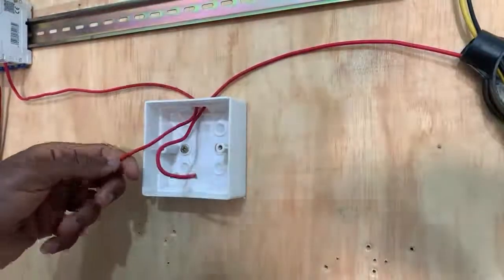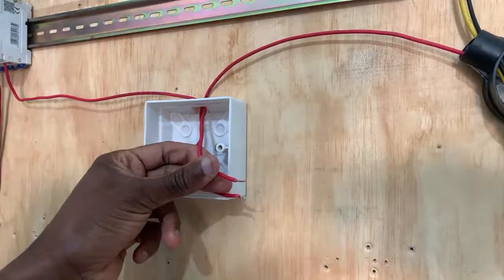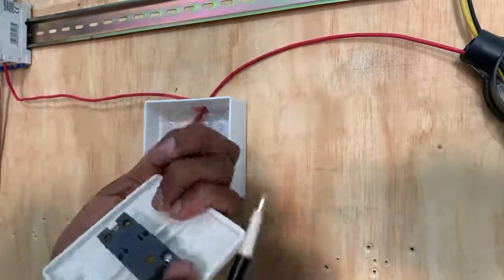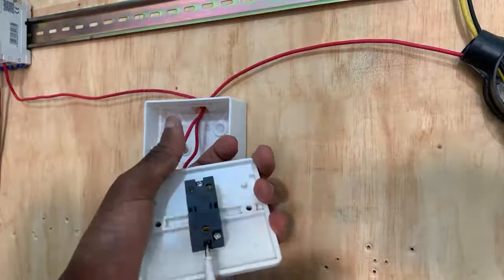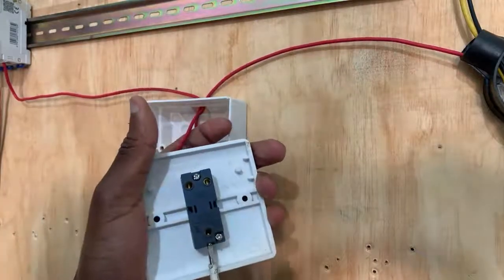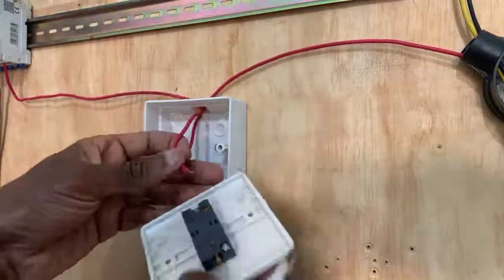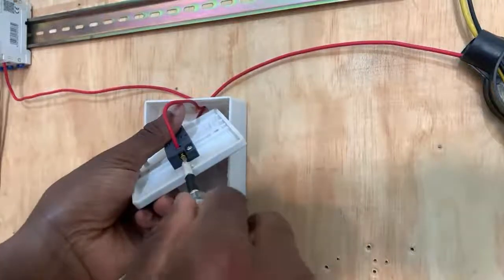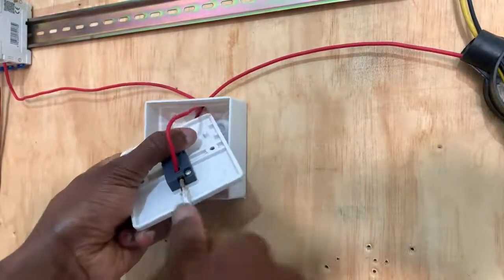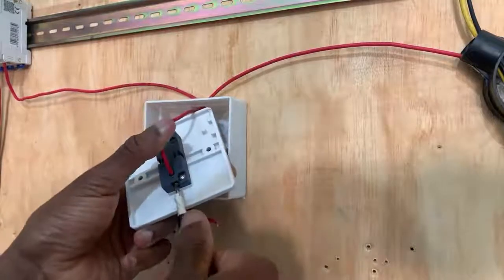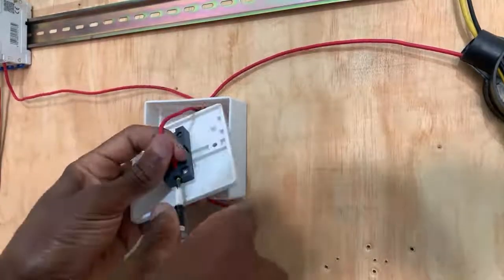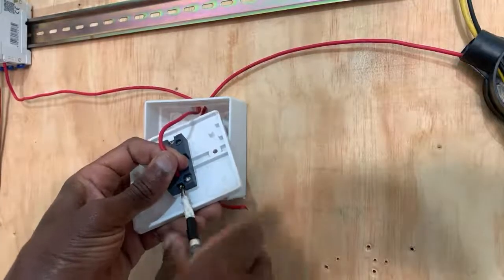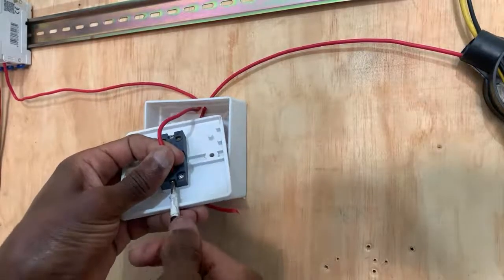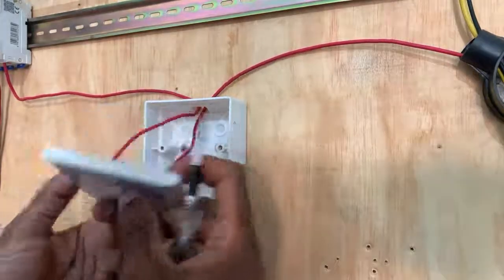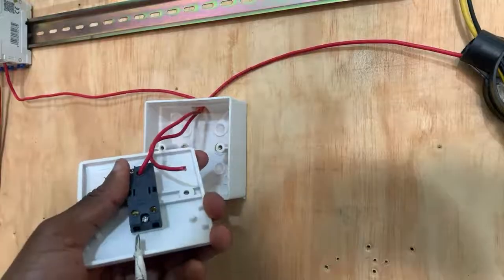So this is the one that is coming from the consumer unit, or from our MCB. I will simply screw the L common properly, then connect the cable coming from the MCB at the consumer unit, and screw it to make sure that connection is definitely tight, so that we don't have an issue in future. An issue may arise due to loose connections, which are a recipe for disaster in electrical installation.